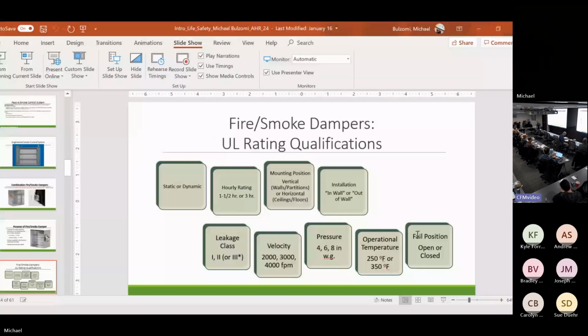I get it. But what could potentially happen is that damper has a UL label on it. The building inspector should be doing their job and should be looking at the submittal and should know if the actuator matches what's on the submittal versus what was actually provided. How many building inspectors are checking that on every single damper, every single job? They're not. So what actually happened was the contractor put non-fire smoke rated actuators on all the fire smoke dampers because they're cheaper. They're not rated properly. The whole reason we factory mount them is to prevent that from happening.